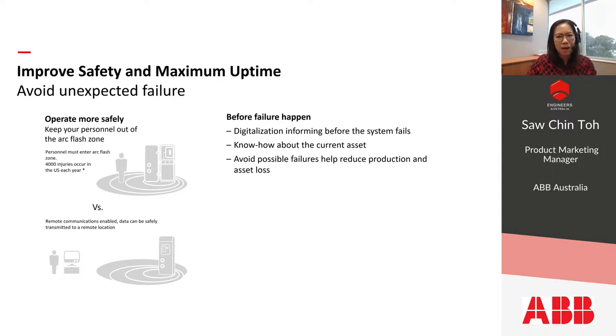We also want to maximize the uptime and avoid the unplanned outage costs. Different industries will have different outage costs, of course. Digitalizing the switchgear will help to detect the common issues before the system fails. Common issues, for example, loose connections or joints, environmental conditions, for example dust or humidity, and faulty installations, can all be detected earlier with condition monitoring. This will help to avoid unnecessary equipment breakdown, and intervention, if required, can be planned at a time with minimal interruption to the plant operation.